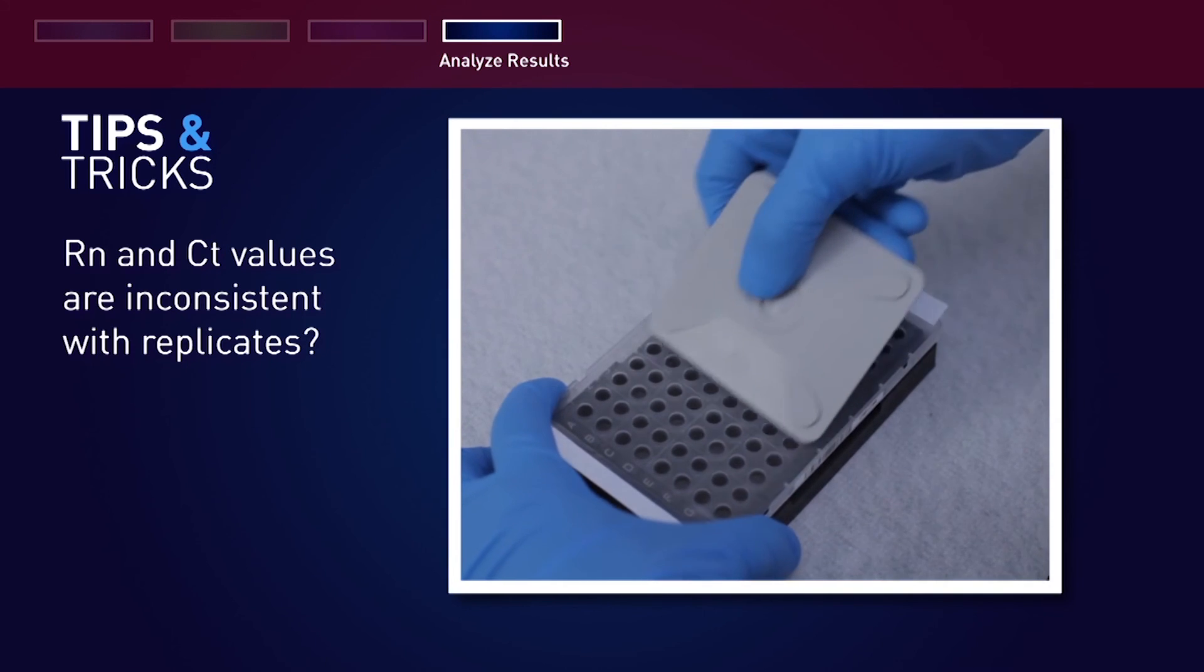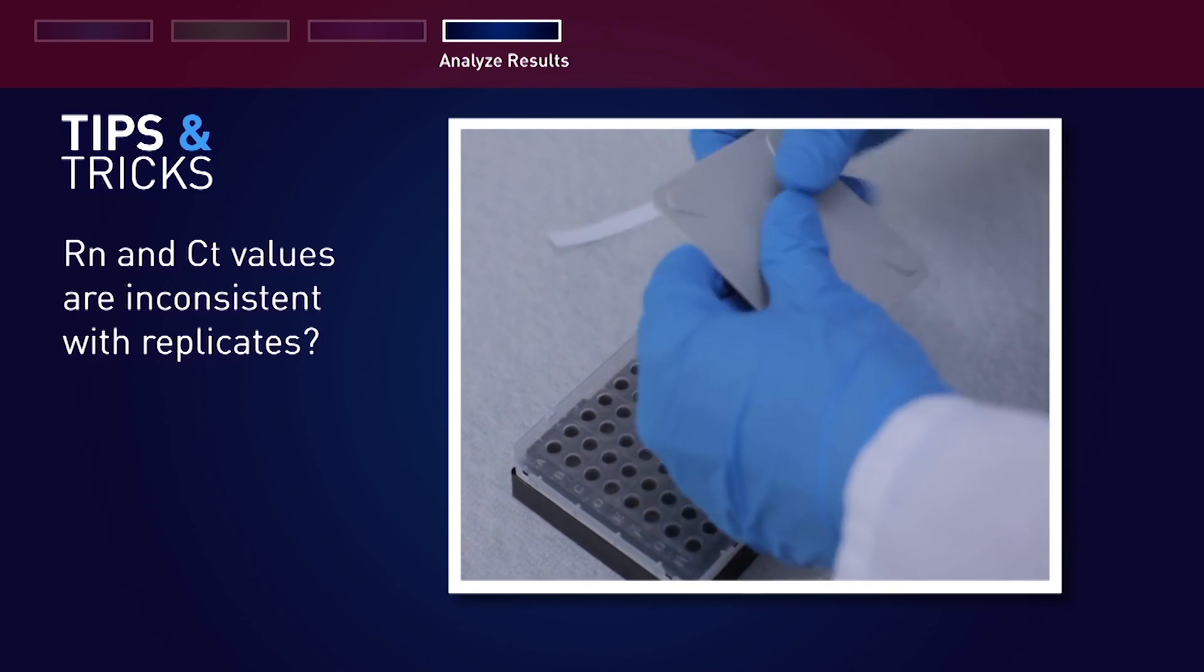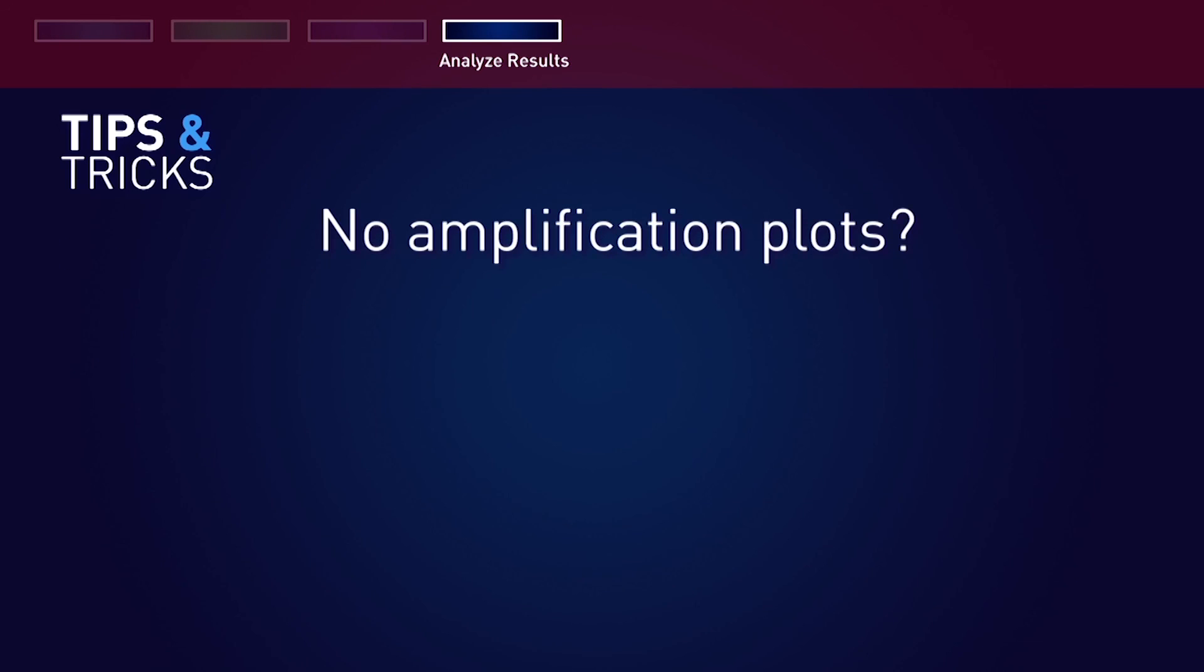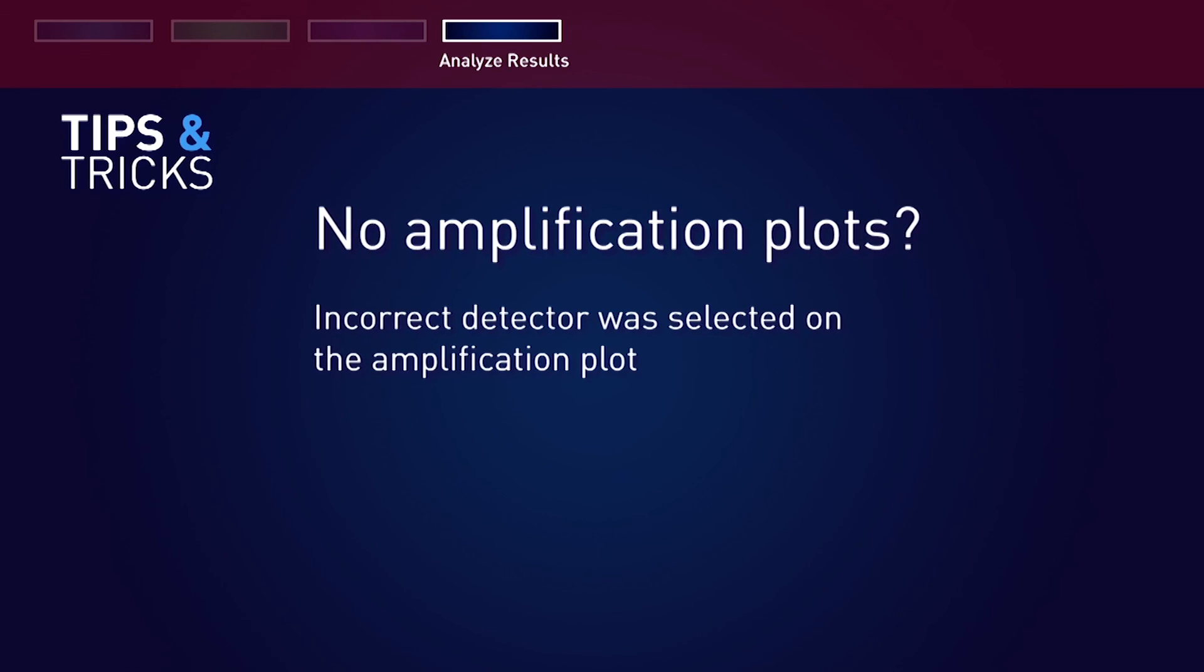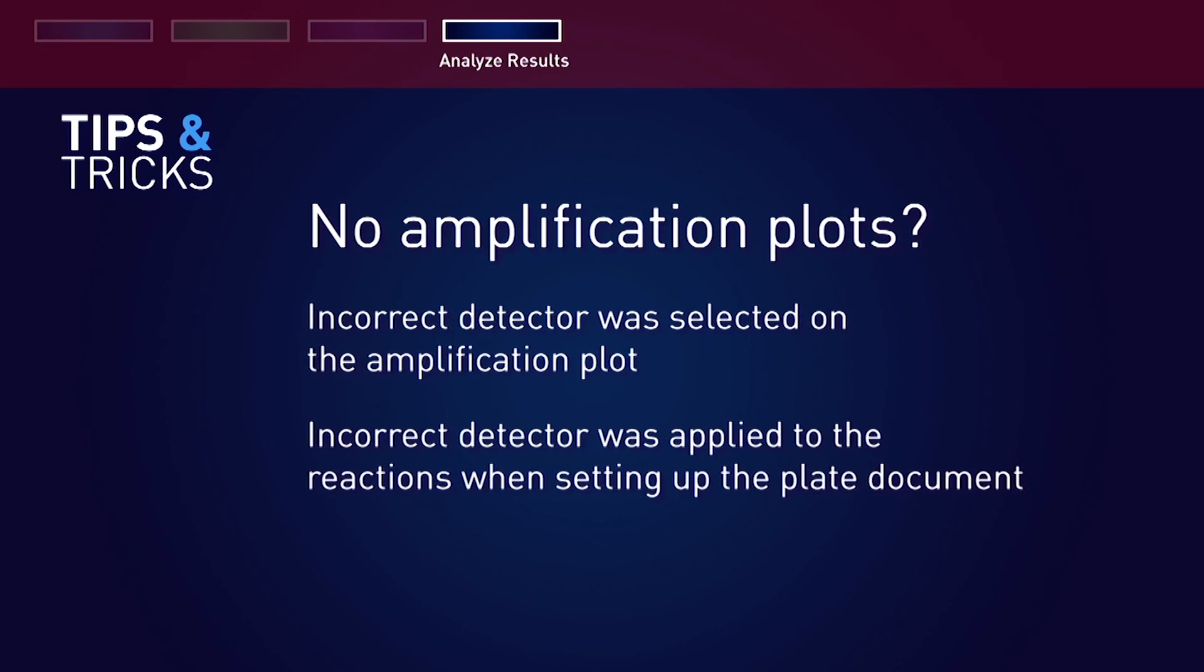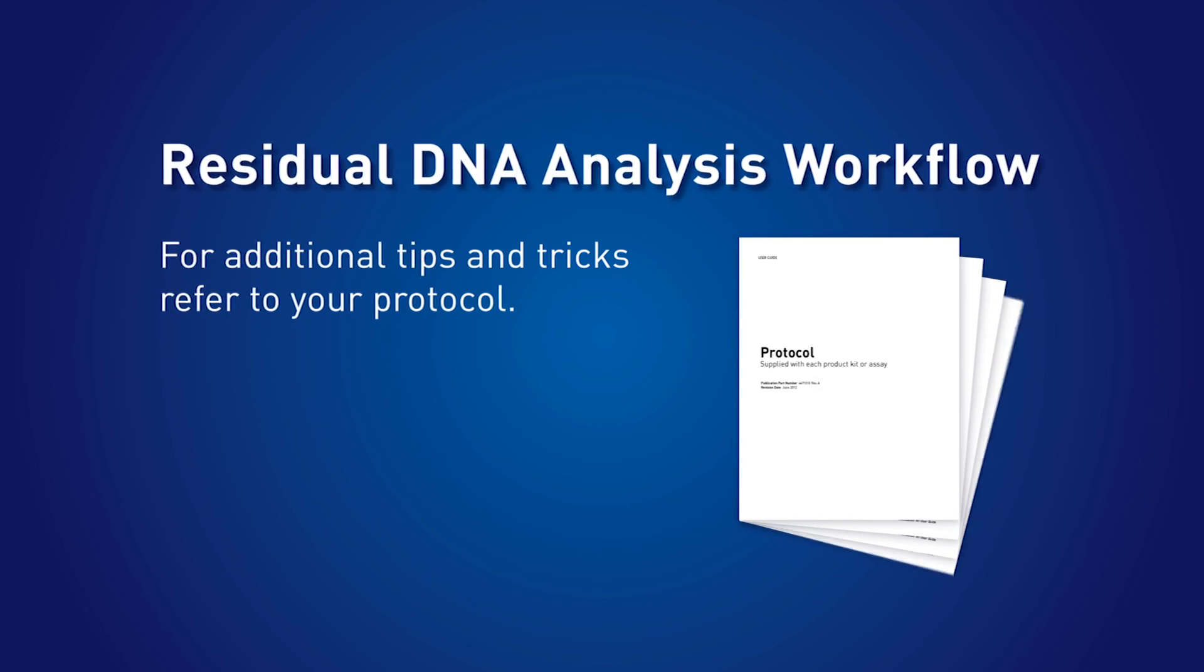If you find that the Rn and Ct values are inconsistent with replicates, it may be there has been evaporation of reaction mixture from some of the wells because the optical adhesive cover was not correctly sealed to the reaction plate. If you find there are no defined amplification plots, it may be because an incorrect detector was selected on the amplification plot or an incorrect detector was applied to the reactions when setting up the plate document. For additional tips and tricks, refer to your protocol.